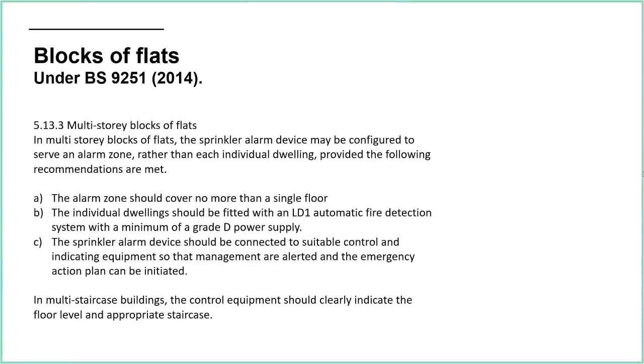Then there's a little sentence at the bottom as well. In multi-staircase buildings, the control equipment should clearly indicate the floor level and appropriate staircase. Again, that's an interesting statement, and I think what they are getting at is that if you've got more than one staircase, then you need some information to tell you which staircase is probably most appropriate to use. So for me, that would probably mean having two zones per floor, to say, is the fire on the left-hand side of the building or the right-hand side of the building? And that would make an impact in terms of which staircase is most likely to be the one that's most appropriate for people to evacuate to.